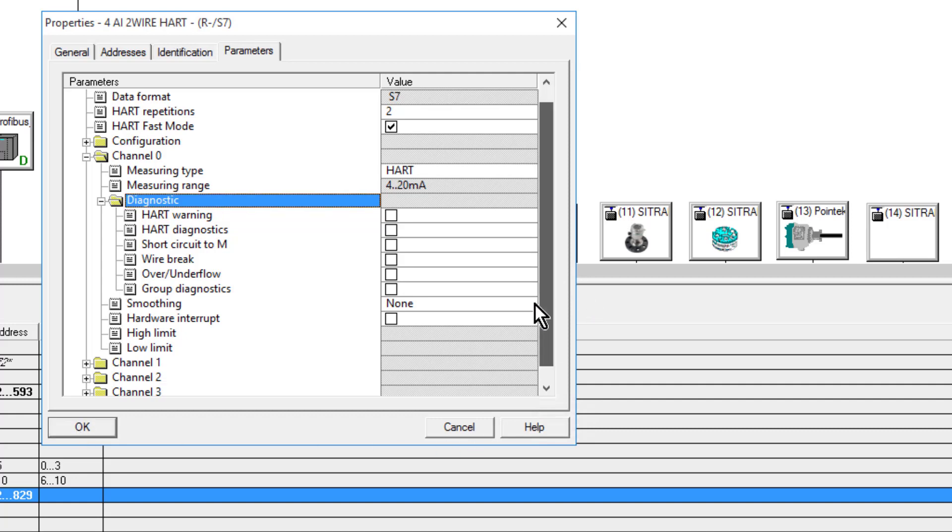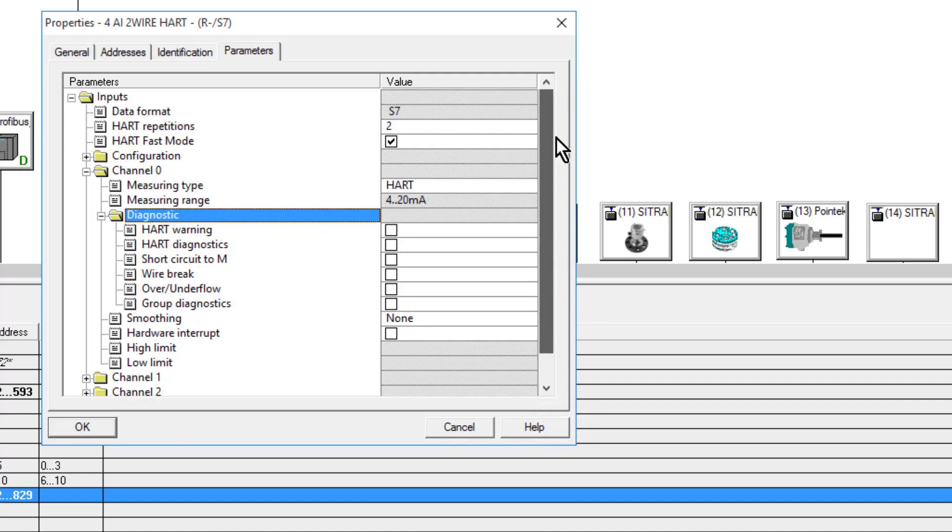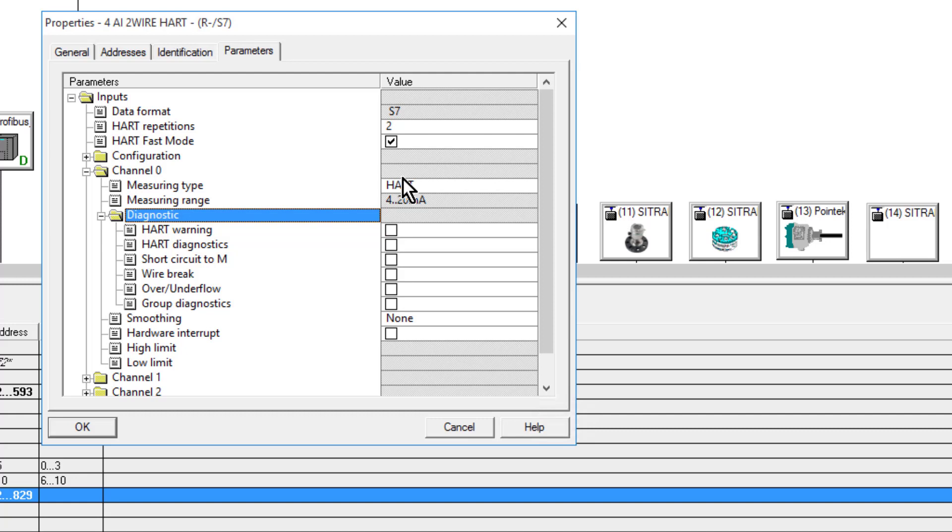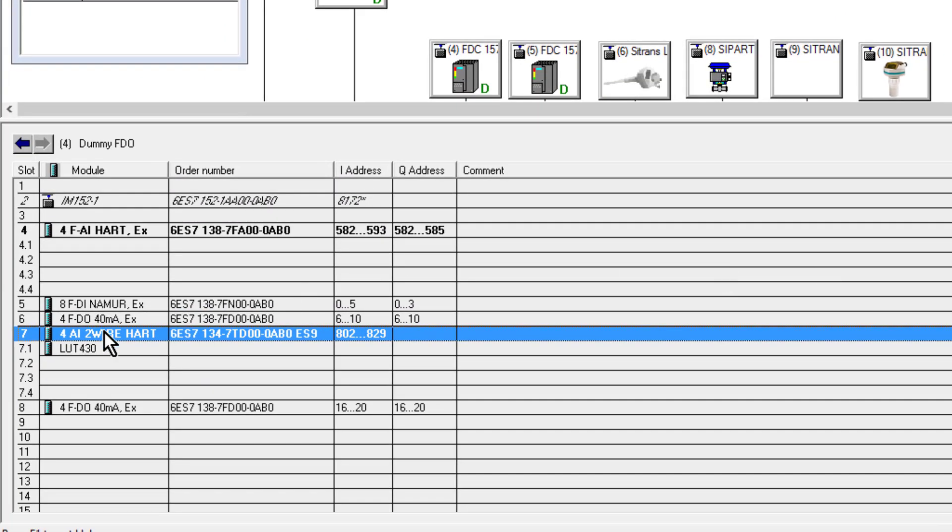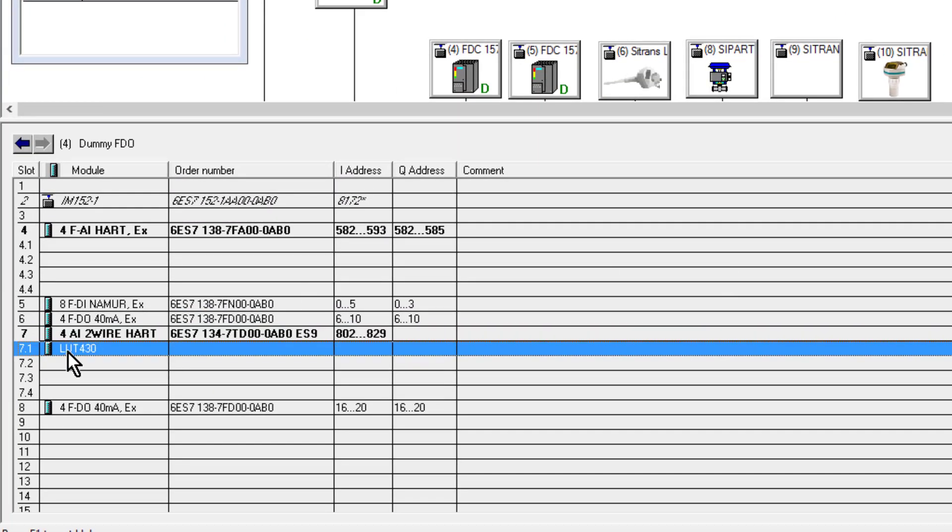Unfortunately, unless you've got configuration in run, setting to HART you would have to do a compile and stop of the automation station or PLC to get that function set up. Really it's something you should enable as standard—it doesn't do any harm. Then when we come to do PDM, we don't have to do any compile or downloads.